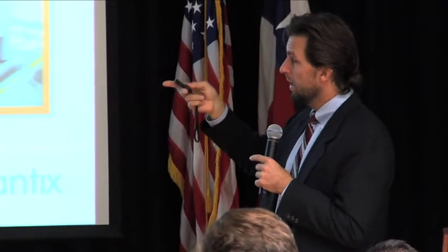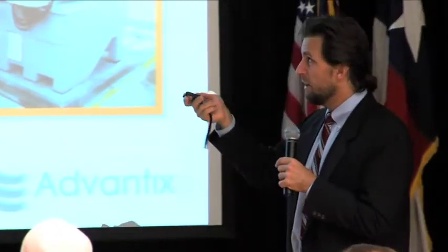It is always clean. So one potential criticism people will say is, well, you've used two pieces of equipment to accomplish what I could have done with one. I could have just stuck a rooftop there and had the rooftop process both the recycled air and the fresh air. And that's a very common approach. My answer is, yeah, that's a 20-ton rooftop right there. If you do the math, in order to process that fresh air on design day and the recycled air on design day, you would have needed a 50-ton rooftop. So go ahead, buy a 50-ton rooftop, or you can buy two small pieces of equipment which are more easily mounted up there and easy to tie together. It's about the same cost, if not less expensive up front, and you're using 40% less energy over the course of the year than you would if you let that 50-ton rooftop inefficiently chug away at that latent load.